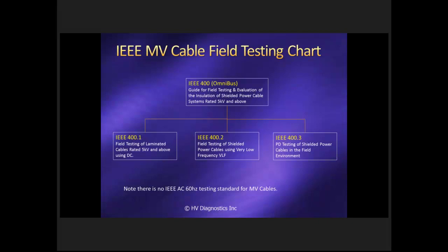The 400.2, which is a VLF standard, includes things like tan delta VLF and partial discharge at VLF. And then the 400.3 document, which is primarily just for PD, includes things like VLF and power frequency. So there's a bit of a crossover between 400.3 and 400.2 when it comes to VLF PD. There's a combination of both of those.